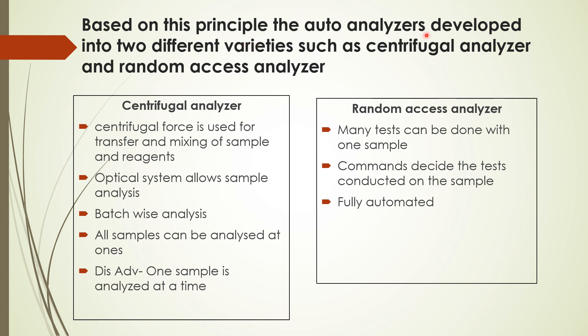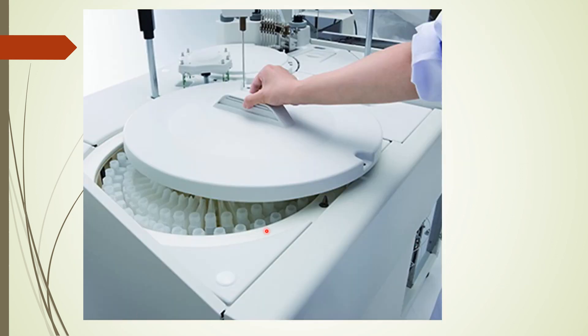Based on the discrete processing principle, auto-analyzers have developed into two varieties: centrifugal analyzers and random access analyzers. In the centrifugal analyzer, centrifugal force is used for transfer and mixing of samples and reagents, with an optical system allowing sample analysis. Batch-wise analysis can be done and all samples analyzed at once, but the disadvantage is only one sample is analyzed at a time for one variable. In the random access analyzer, many tests can be done with one sample, the commands decide the test conducted, and it is fully automated.